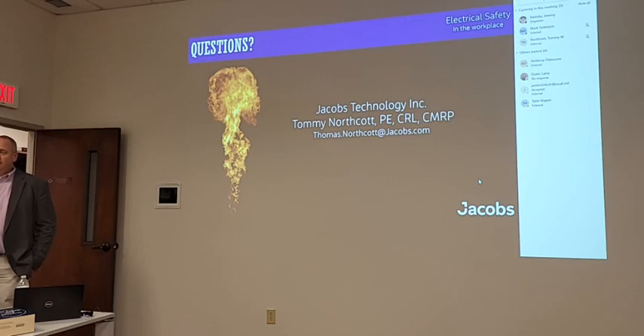You see a whole lot of OEM equipment, and it comes in with a disconnect enclosure. There's a main breaker and there are the starters and other components in there, and you've got plugs on the outside of it. You see a lot of that. So I guess you would have to have the sticker that represents the line side of the breaker, but if you've got starters inside there on that load side, that's what you're making and breaking when you push that start or stop button. And so you would probably need to have two stickers in that case, wouldn't you?